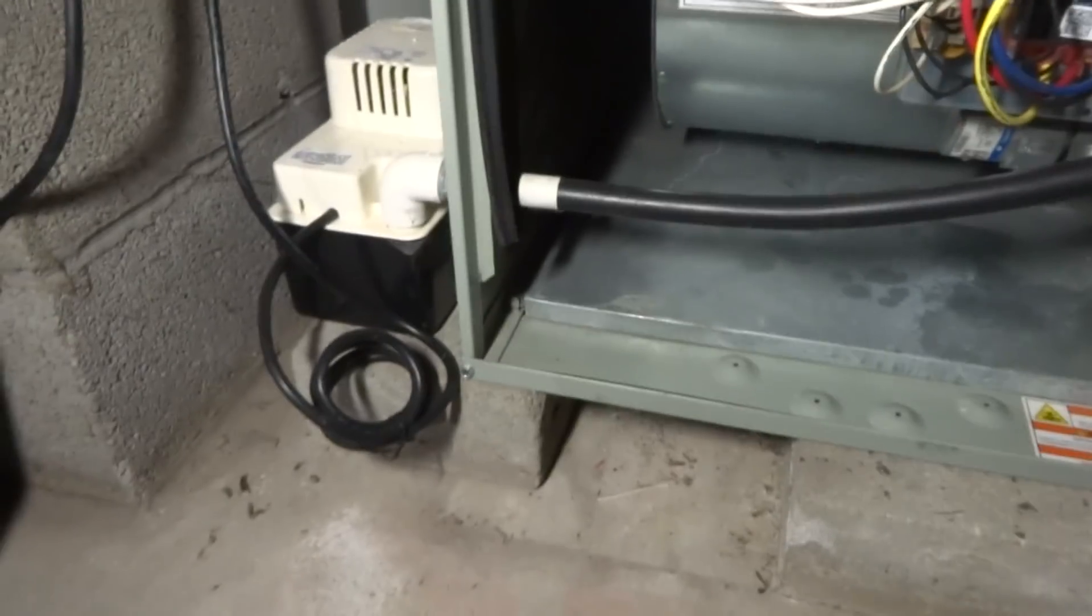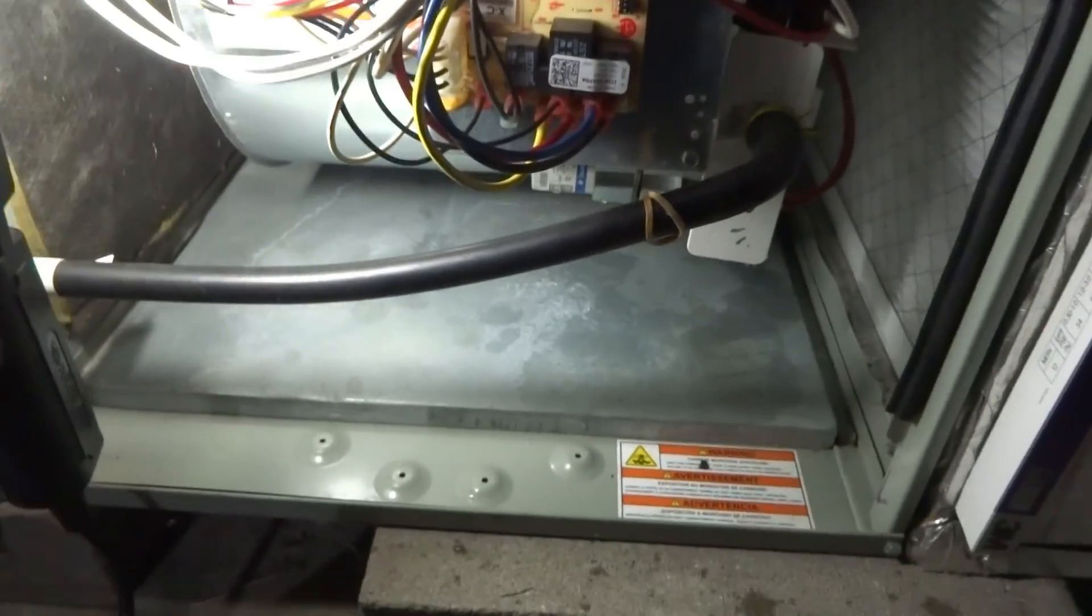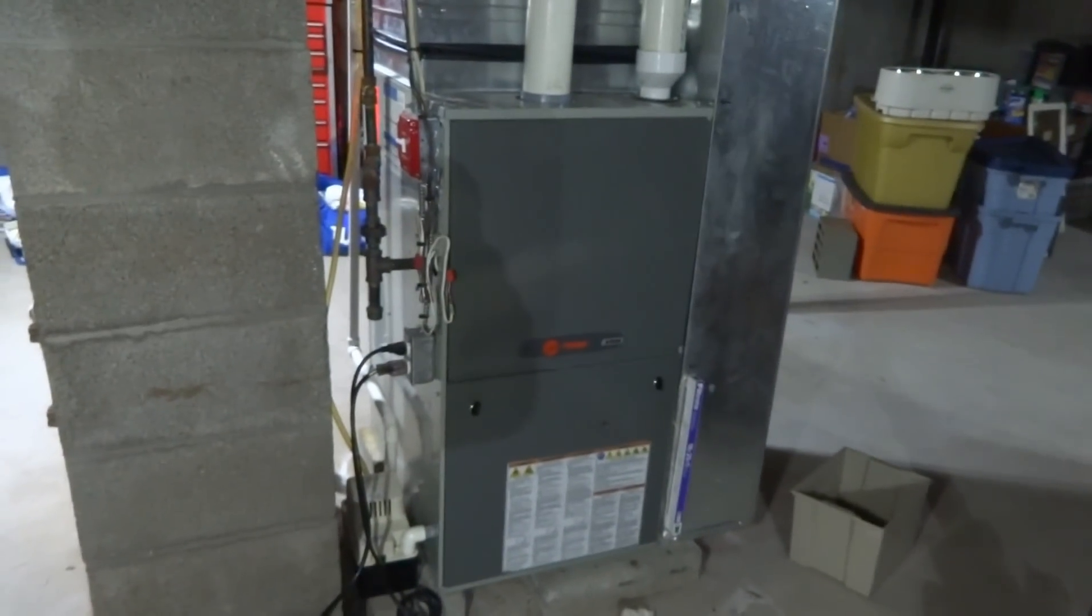As long as it works, right? Yeah. Good. Clean flame sensor. Clean condensate drain blockage. That was in there. It's almost like rubber. I don't know what it is. Running good now.